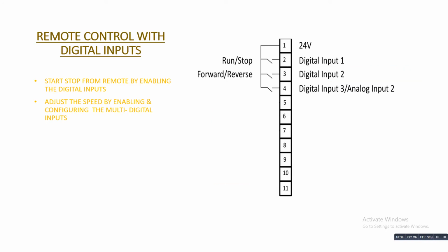The next one is remote control with digital inputs. As I told you, for remote control you have to select the remote mode, or you have to configure the remote mode. So you can start and stop the VFDs by enabling the digital inputs. You can see there are multiple inputs available. Each input you have to configure in the VFDs, what it must be, what it should enable. Example, digital input 1 start or stop or forward, digital input 2 reverse, digital input 3 some kind of speed set. So you have to refer to the manual to set these digital inputs.